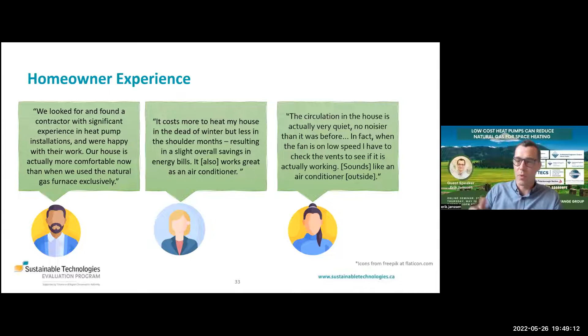Say our goal was to create the absolute lowest cost of operation for our heating systems, since a lot of people are primarily motivated by the financials. There are ultimately two things that impact the cost of operation for an air source heat pump, as we saw in that equation earlier: the utility rate, and in Ontario we have time-of-use rates that change throughout the day, and the efficiency of the heat pump, which goes down as it gets colder outside. Each heat pump also has its own manufacturer efficiency curve, with better heat pumps having greater curves. The point is that both our electricity rate and heat pump efficiency really change on an hourly basis throughout the day.